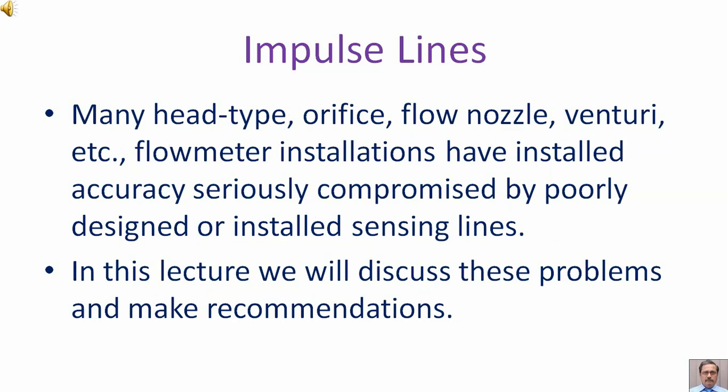Many head type, orifice, flow nozzle, venturi etc. flow meter installations have installed accuracy seriously compromised by poorly designed or installed sensing lines. In this lecture, we will discuss these problems and make recommendations.